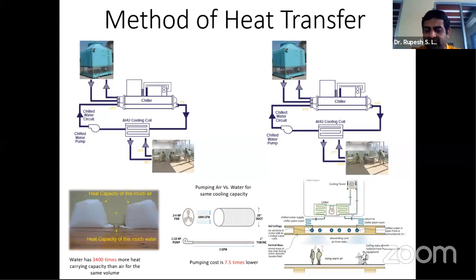Second is coming to the method of heat transfer. I think it's basic physics that we all know that the heat capacity of water is almost 3,400 times that of air. That means this much water, as you can see, this small miniature glass, will be equal to these two big bags of air. So if this much water can remove the same amount of heat that these two big bags of air can remove, then shouldn't we look at a way of removing heat from an indoor space using water rather than air? So that's where the process of air conditioning would come into play.